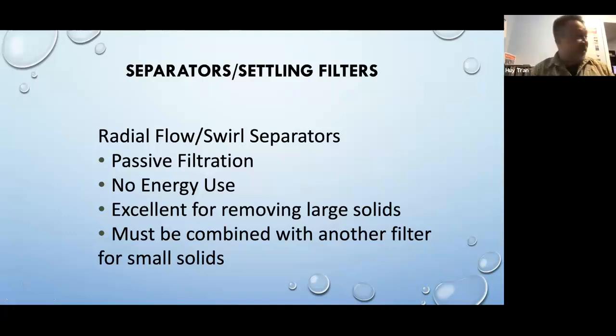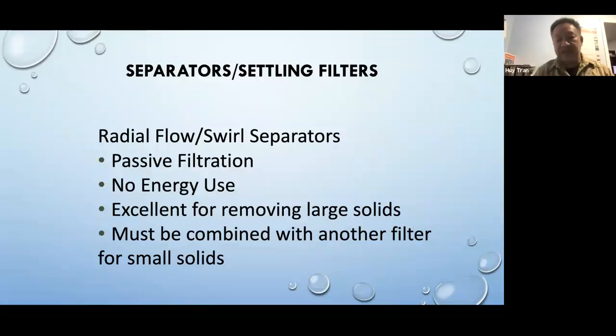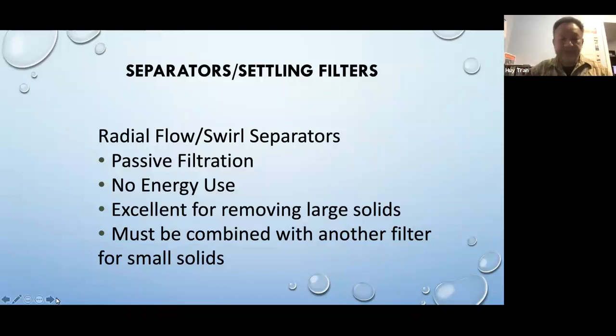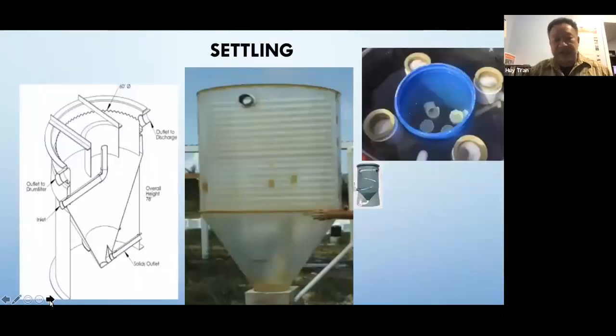Another filter option is the radial flow swirl separator, a passive filtration device with very low energy usage. It does an excellent job removing large solids, but usually needs to be combined with an additional filter for smaller particles — at best it handles particles down to about 400 microns, and anything smaller may pass through.